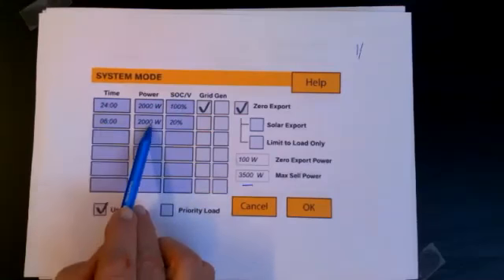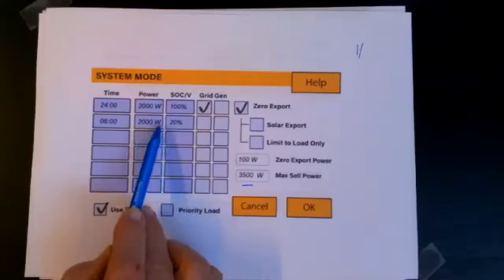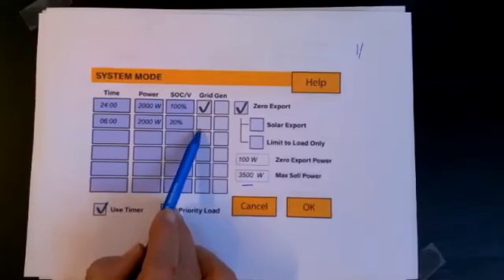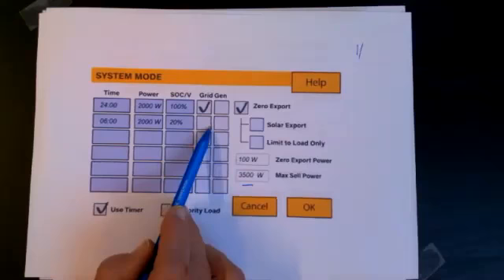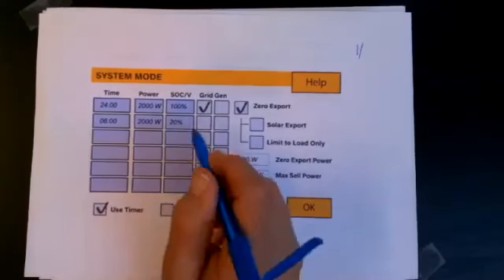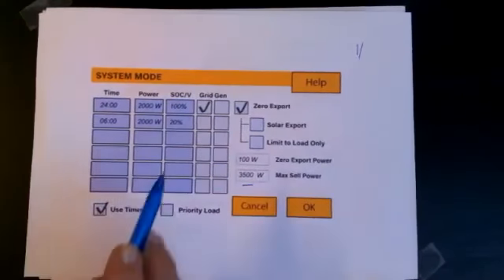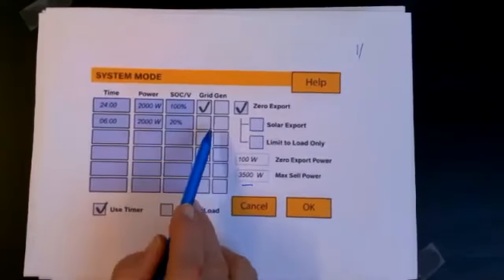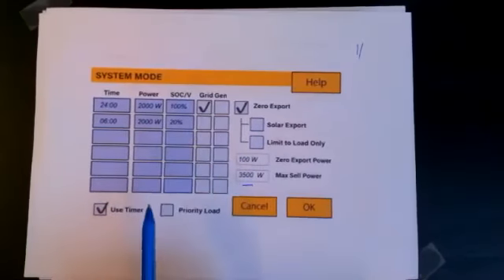At 6 o'clock, okay, I want to stop it. I want to allow it to 20%. So this is a stop signal. This means stop, because there's no tick on here or here. We are going to add it and put a tick on it, because it does cause some confusion. With no tick, it means stop. With a tick, it means start. So this always does cause a problem. It does take a bit of getting used to the controller, and that was one of the reasons we have made the change. On version 4.16, you will see it's much easier to work with.